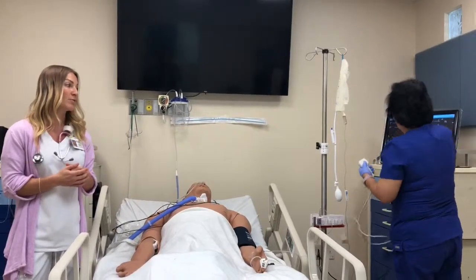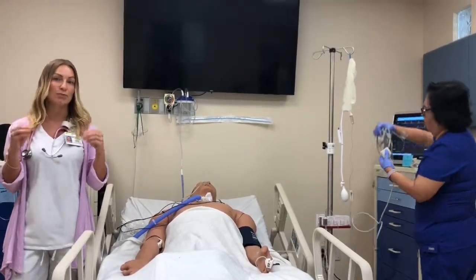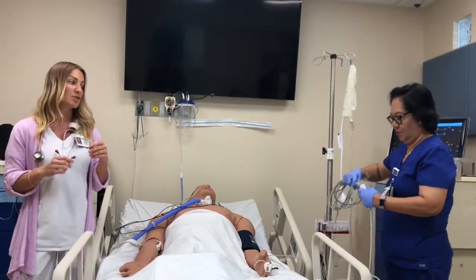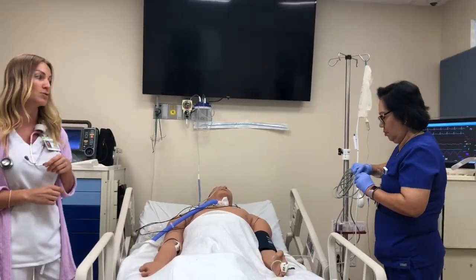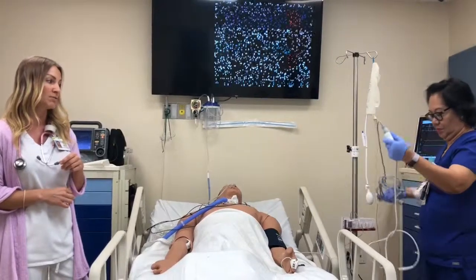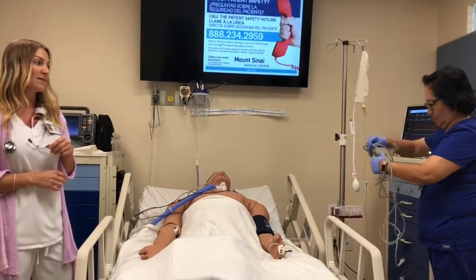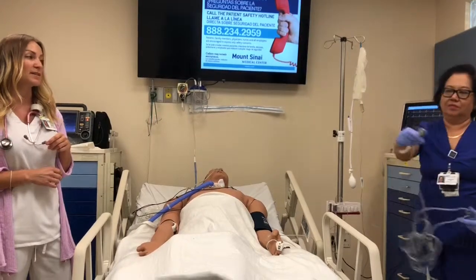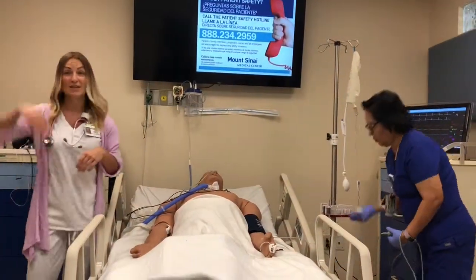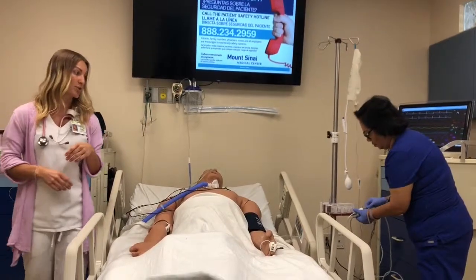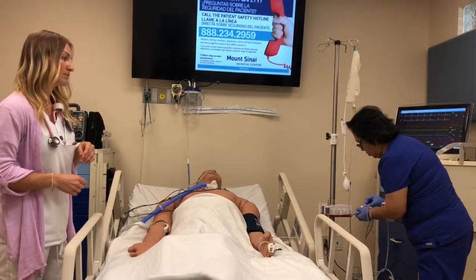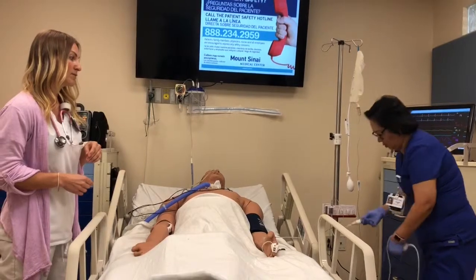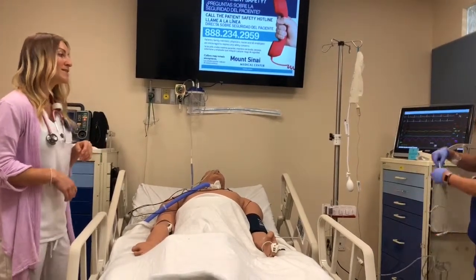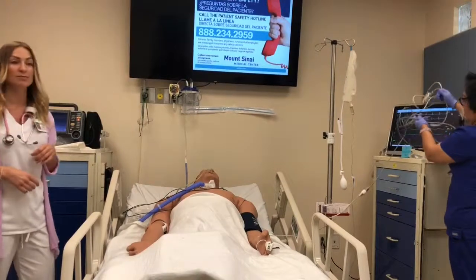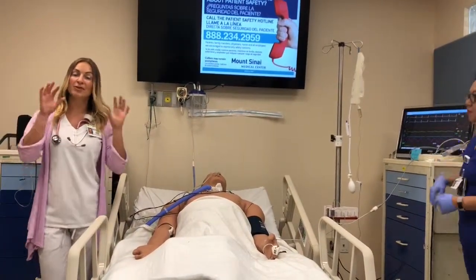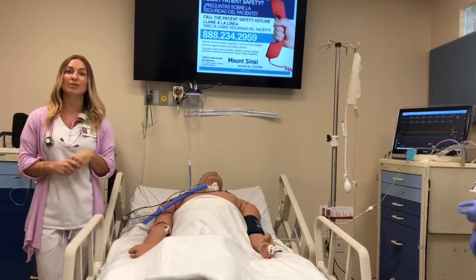At the end of the primary cable, there are dual inputs that you can place multiple cables in. So you're going to connect that secondary cable to one of those dual inputs, as so. And then the distal end of that secondary cable will fit into the tail of your transducer portion. As so. Beautiful. Once this is fully connected into your Spacelabs monitor, it will flash open a new column showing that arterial waveform.